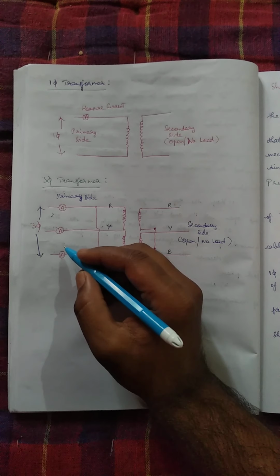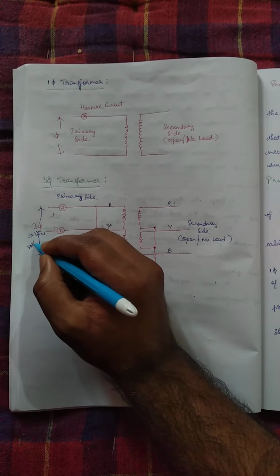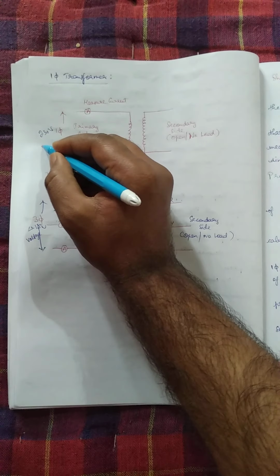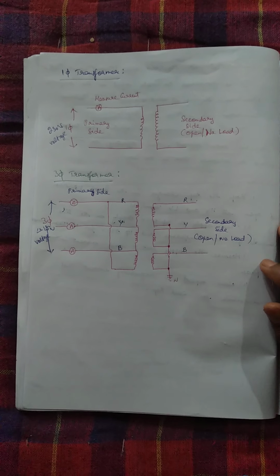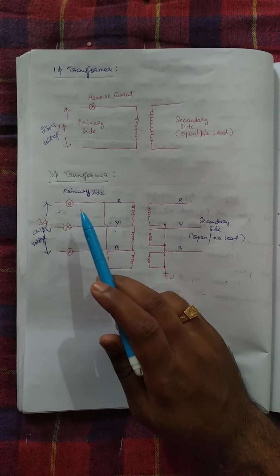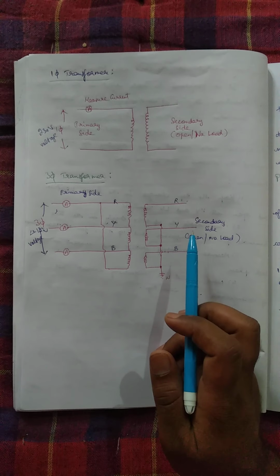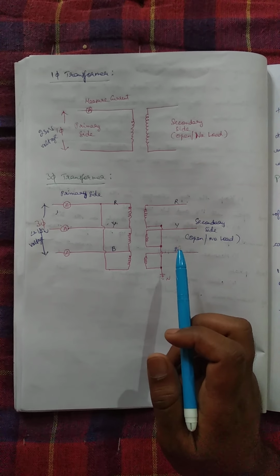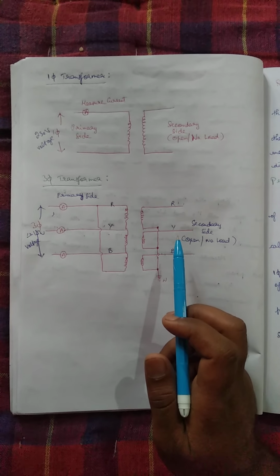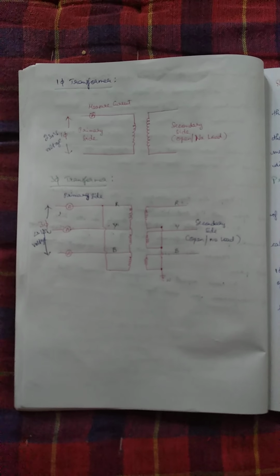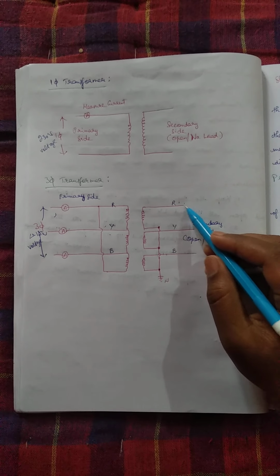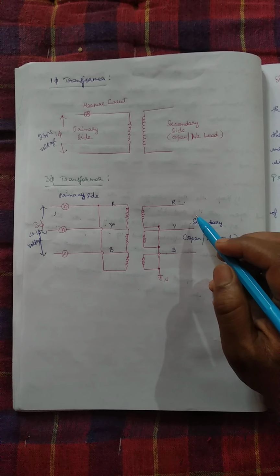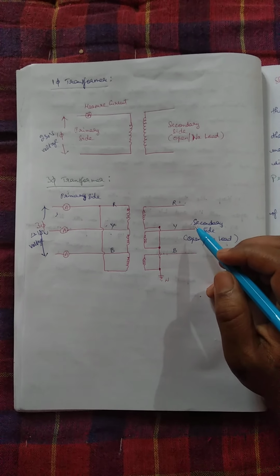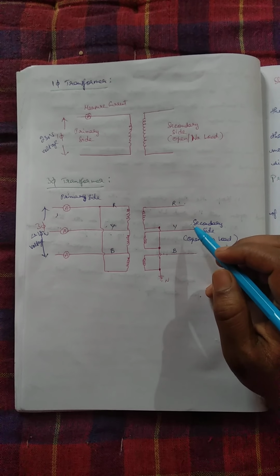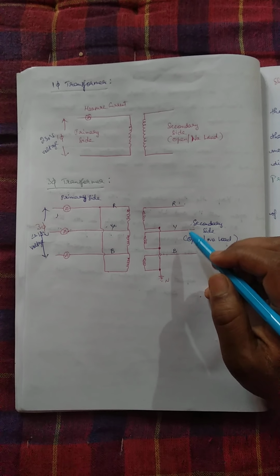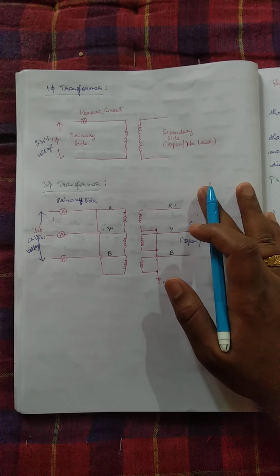Here I will mention the voltage as 415 volt, three-phase voltage, and measure the current of each phase. Here the secondary is kept open. So you should be very cautious, because with the secondary side kept open, if any person unknowingly touches it, it will automatically behave as a short circuit, which will be very dangerous for the human. So you should be very cautious during this test. This is the basics of the magnetizing current test.